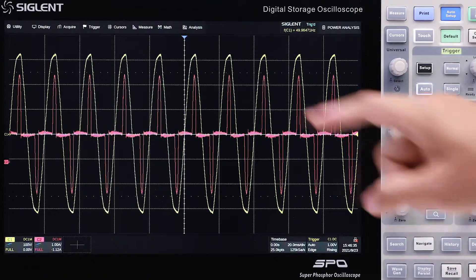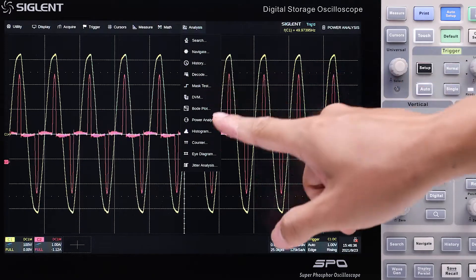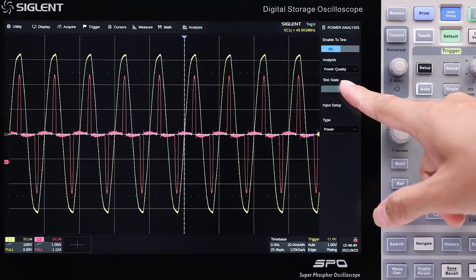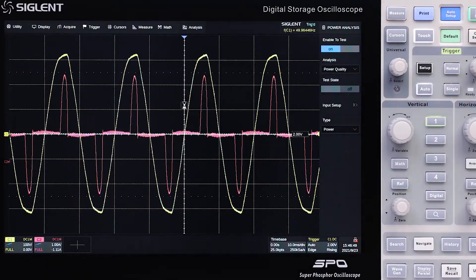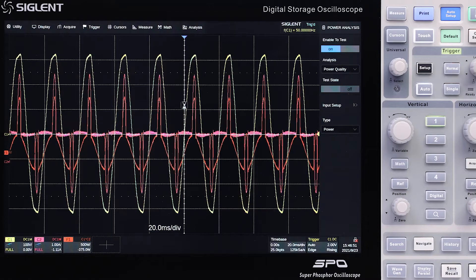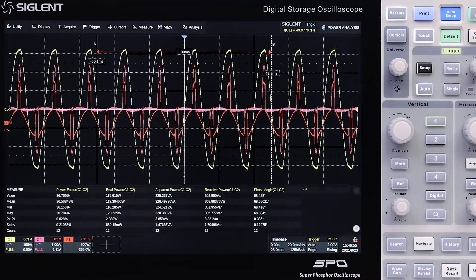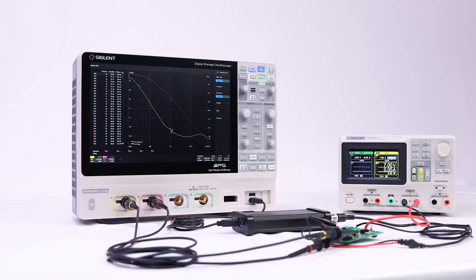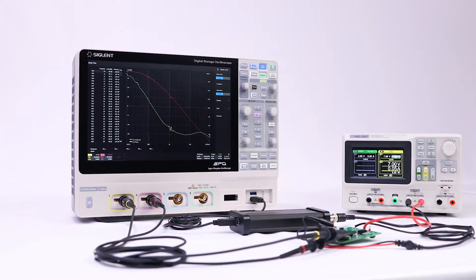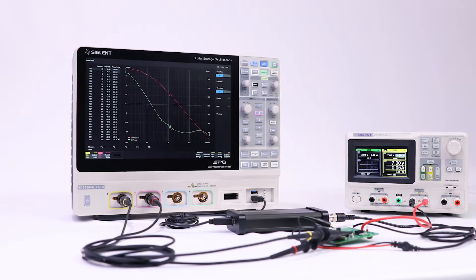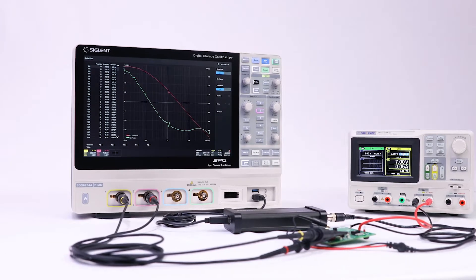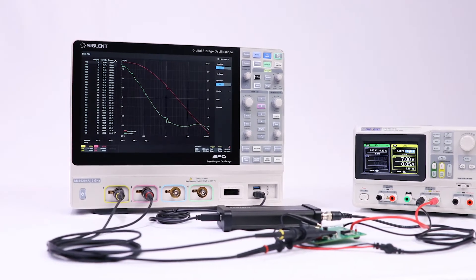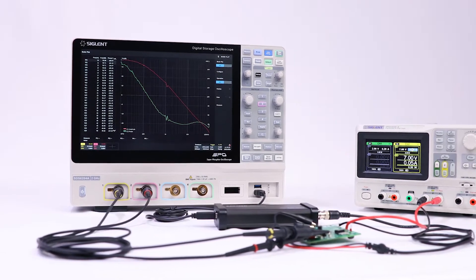The power analysis option improves efficiency by letting the scope perform the numerous calculations required. With standard Bode plot, power supply control loop response can be measured without an expensive network analyzer.